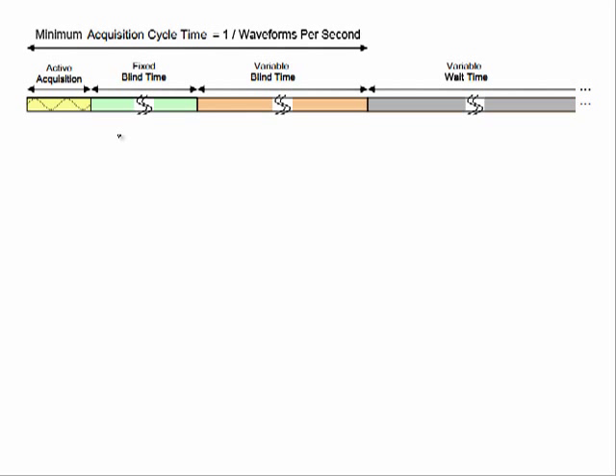First, I wanted to look at a typical diagram of an acquisition cycle of a DSO. You can see it's broken into four basic sections. The first one is the actual acquisition period, which is started by the reception of some kind of trigger. And then the acquisition time itself, which is based either on the time-base setting and the number of divs or sample length, whichever happens to be longer in real time.